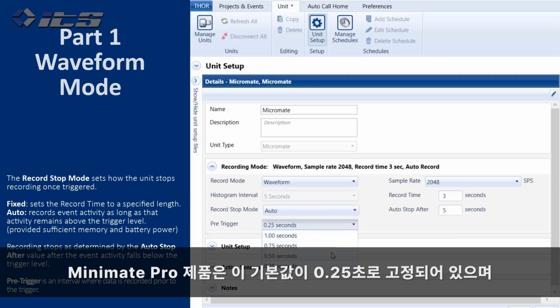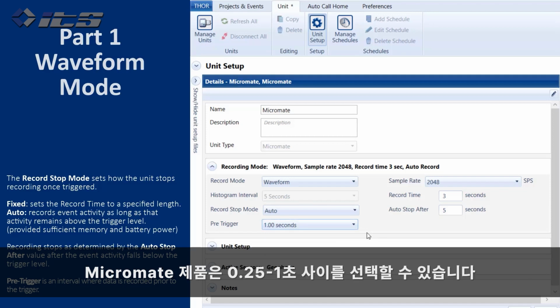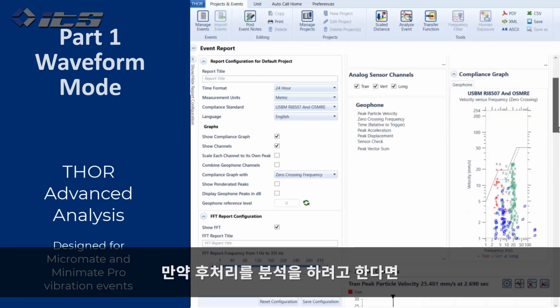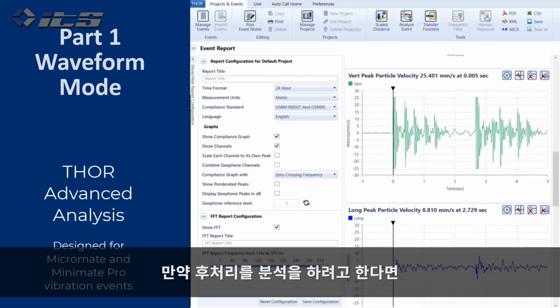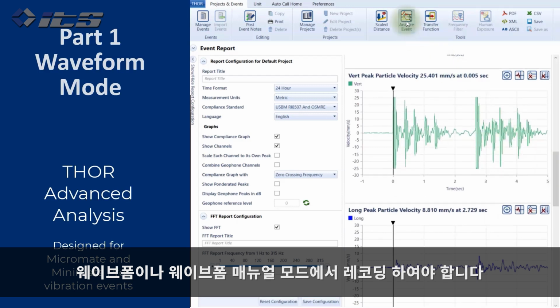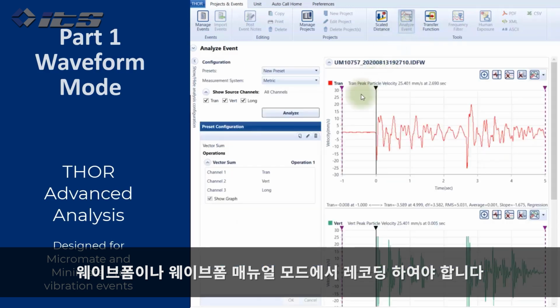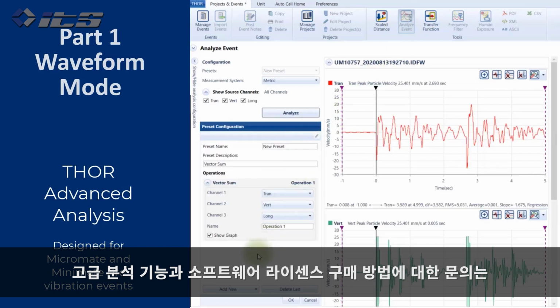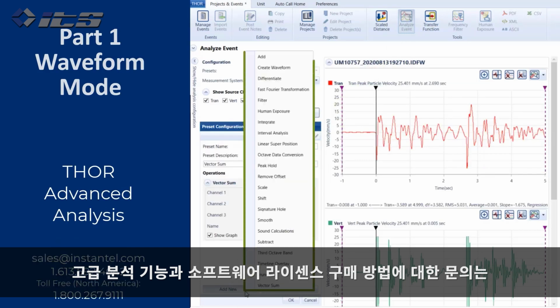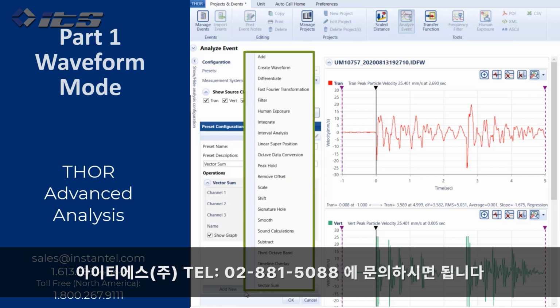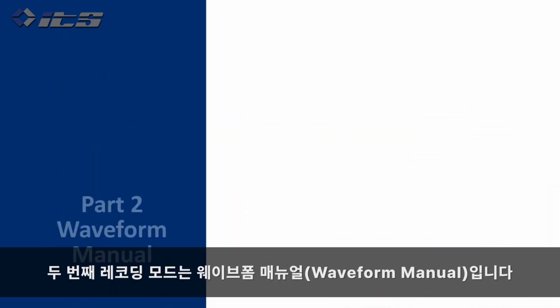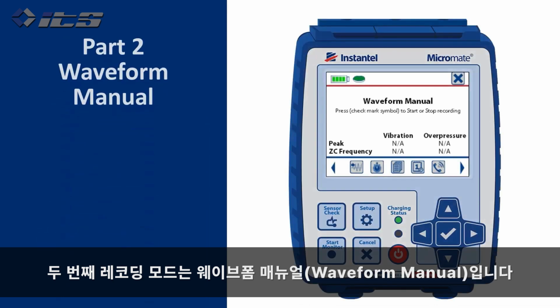Minimate Pro units are not programmable and are set by default to 0.25 seconds. The Micromate units can be set from 0.25 to 1 second. If you plan on doing post-event advanced analysis, then you must record in either waveform or waveform manual mode. For more information about advanced analysis and how to purchase an advanced software license key, please contact your Instantel sales representative.